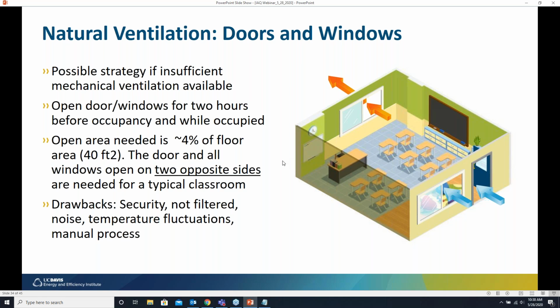Again, there are some drawbacks here. Security is a concern. The air is not filtered. There may be noise and temperature fluctuations, and you've really got to work with the teachers and school staff to make sure they're opening those windows and doors 2 hours prior to occupancy and keeping them open all day.